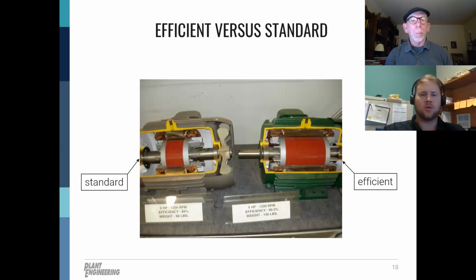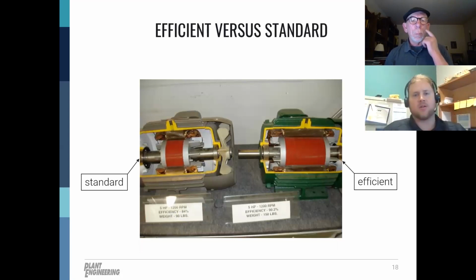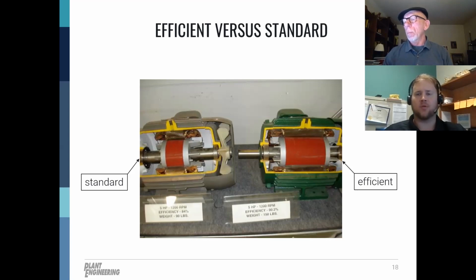So I have a few slides on efficient motors versus standard motors. So here you will see a display. This is a standard induction motor compared to generally just a higher efficiency motor. And actually these cutouts are here at our lab in Raleigh, which I'm sitting in right now. This slide is more representative of older induction motor design versus newer, because today all covered induction motor products that are sold in the US are required to be NEMA premium efficiency levels. In Europe, the requirement is called IE3 level. A few things to note, just looking at the comparison from the motor on the left to the motor on the right. The efficient motor has a smaller fan and also has more stator and rotor laminations.